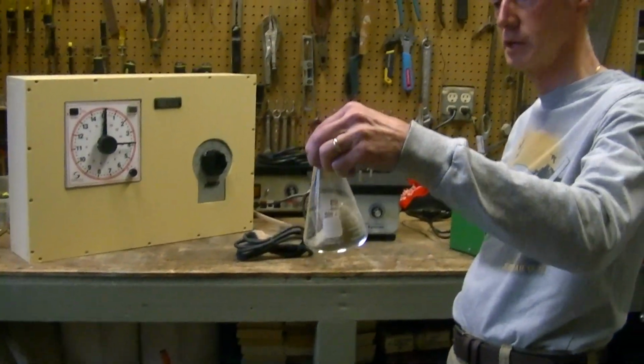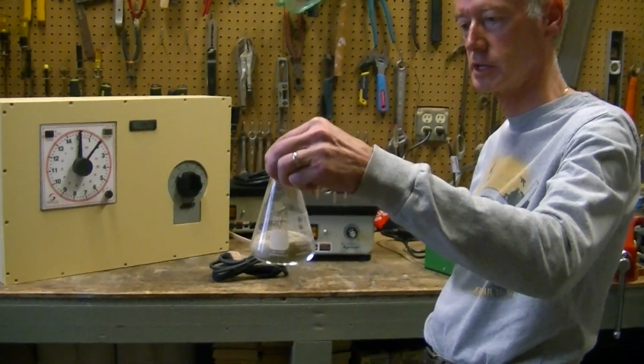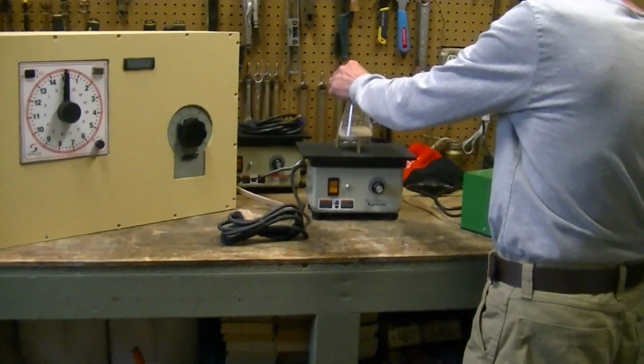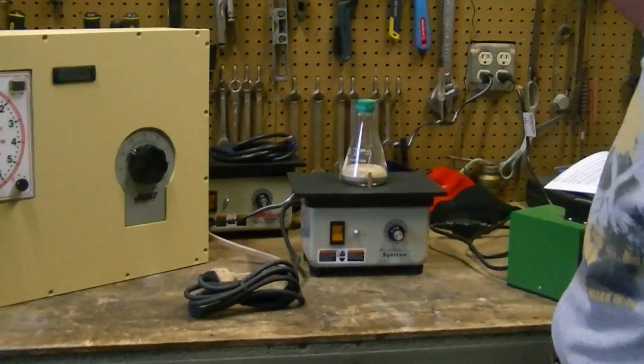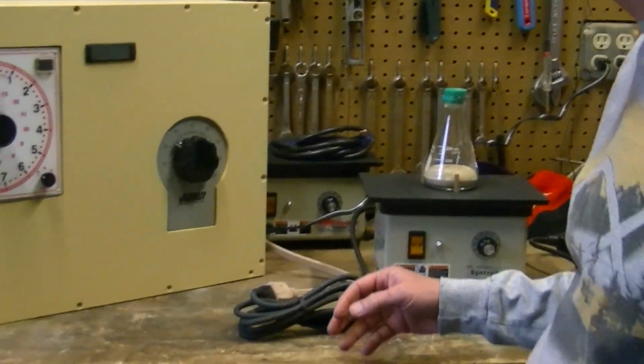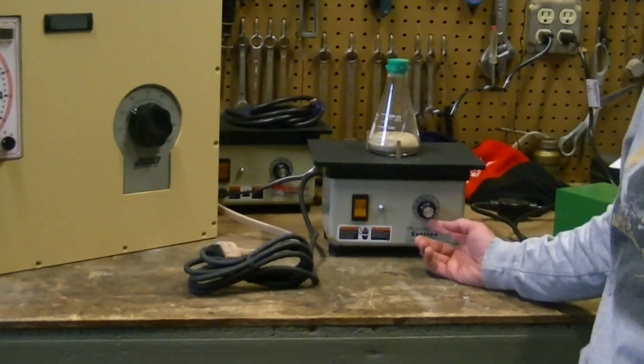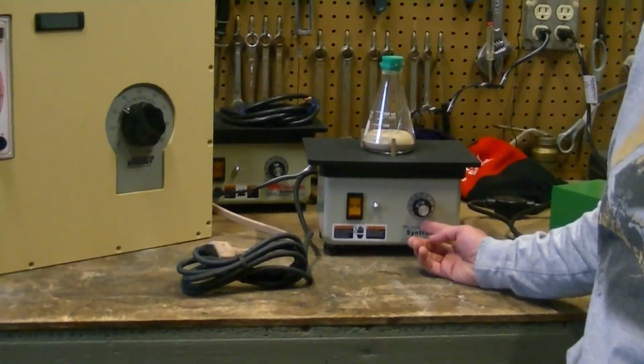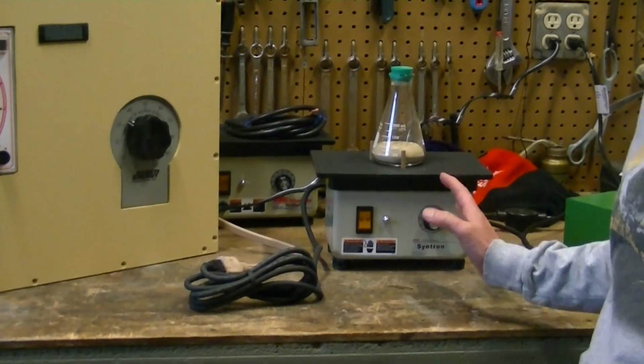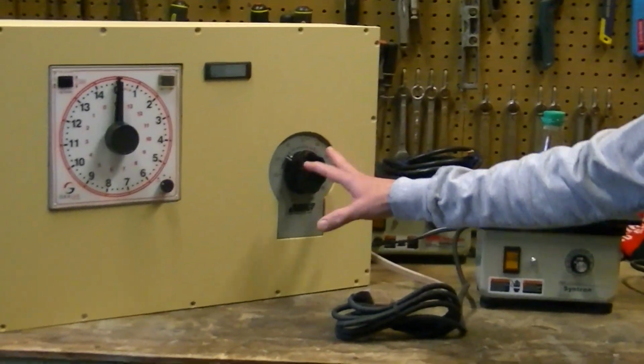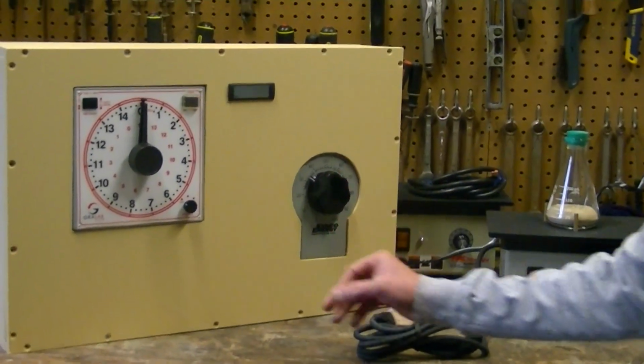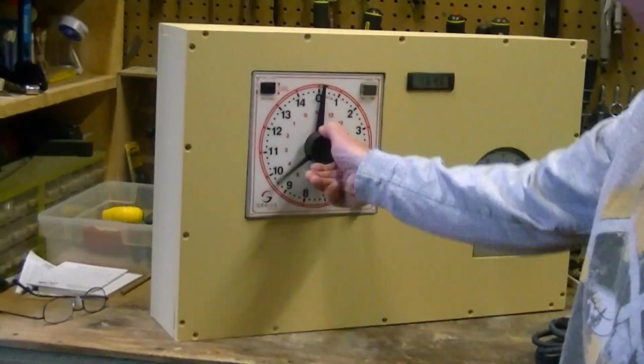And once you get that done, you just kind of center it. Set it on the vibrating table, and the vibrating table is always set at the maximum setting, which is 100, and you're going to do all the control through this. So once you get it calibrated, you're not going to change that. So you're going to turn the timer at 15 seconds.